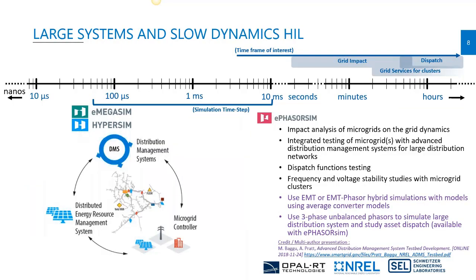For large systems and slow dynamics HIL testing, you test microgrids or clusters of microgrids within a large power system to study whether they can provide grid services using an aggregator. It is also possible to simulate large distribution networks with three-phase unbalanced networks when studying slow dynamics. eMEGASim and HyperSim provide EMT-type simulation, and ePHASORSim enables phasor-domain simulation — balanced or unbalanced — which is particularly useful for running large distribution systems in real time.